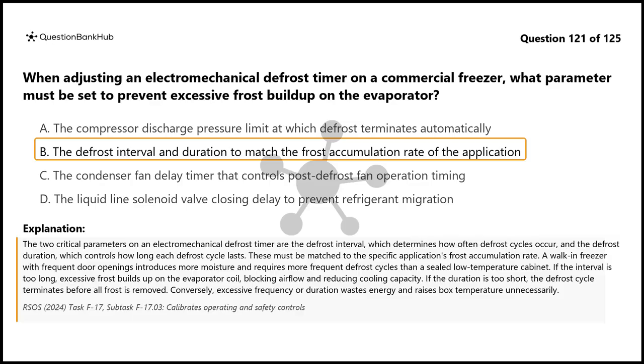A walk-in freezer with frequent door openings introduces more moisture and requires more frequent defrost cycles than a sealed low-temperature cabinet. If the interval is too long, excessive frost builds up on the evaporator coil, blocking airflow and reducing cooling capacity. If the duration is too short, the defrost cycle terminates before all frost is removed. Conversely, excessive frequency or duration wastes energy and raises box temperature unnecessarily.